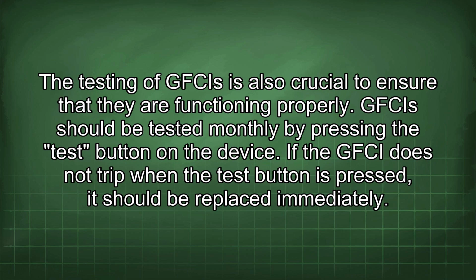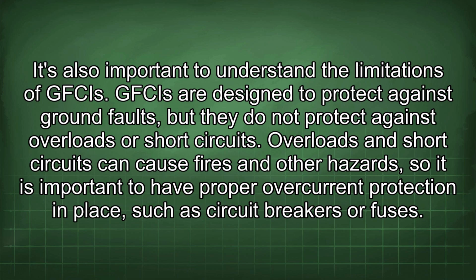The testing of GFCIs is also crucial to ensure that they are functioning properly. GFCIs should be tested monthly by pressing the test button on the device. If the GFCI does not trip when the test button is pressed, it should be replaced immediately. It's also important to understand the limitations of GFCIs.